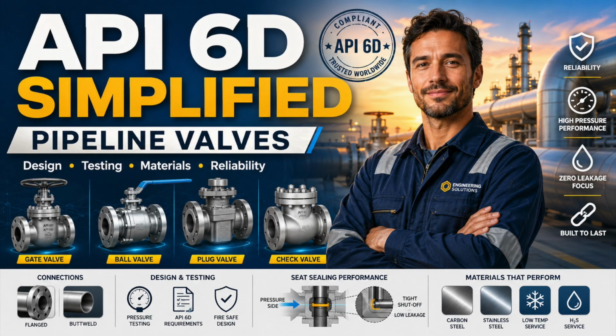Design control matters for the same reason. Inside one valve, pressure loads move through the body, seats, closure member, stem, bolting, and actuator interface. Change seat preload and leakage may improve, but operating torque may rise. Change elastomer and low temperature performance may improve, but decompression resistance may worsen. Increase wall thickness and weld end geometry may need to change. Change material and welding procedures may need revision. Change actuator torque and stem loading may increase. Change bore and pigging compatibility may change.